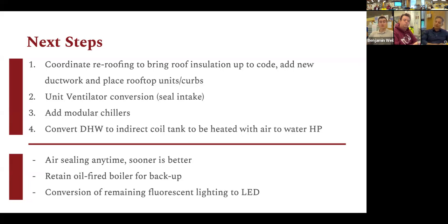Step number three would be adding the air to water heat pumps / modular chillers. That would just be as simple as having pipes that go to your existing hydronic system with the circulator pumps. And then finally, an extra thing would be to have an indirect coil running from those heat pumps to the domestic hot water tank, which is currently electric resistance. Some other miscellaneous things are the air sealing, which could happen at any time around that, the rim joist air sealing, and the roof to wall interface. We propose keeping the oil boiler for backup. And finally, we saw some fluorescent lighting that we recommend switching to LED fixtures.